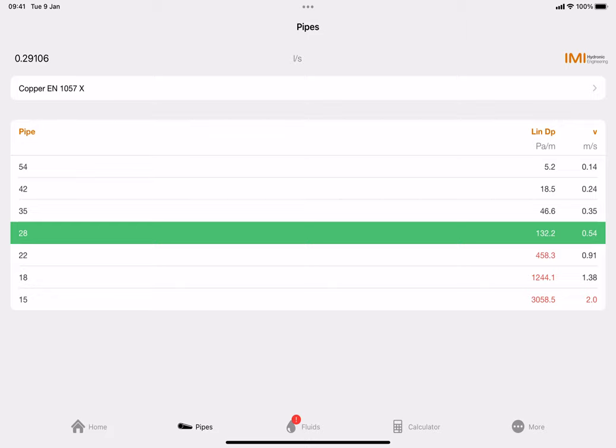Now we make an engineering decision. Let's say we've got about seven or eight meters of primary pipe work. Our target velocity was one meter per second and we're at 0.91 - that's about as close as you're going to get, almost perfect. But we've got 458.3 pascals for every one meter of pressure drop. If we had eight meters, that's 458.3 times 8 - still only about 3,700 to 4,000 pascals, and we've already got 50,000 pascals available. So you ask yourself: is 22 millimeter sufficient for this heat pump upgrade? The calculations don't lie - yes you could use 22 millimeter pipe work as long as your runs aren't too long.